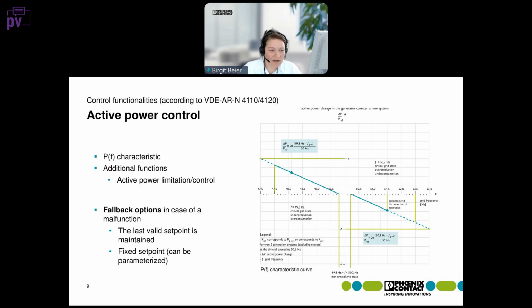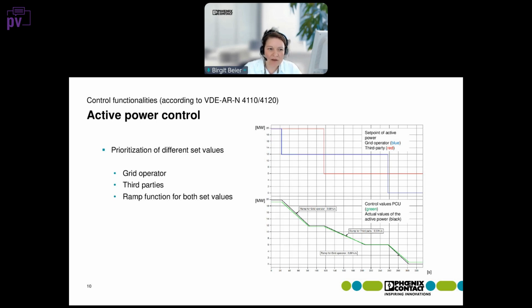So what else do you have? You have some fallback options in case of malfunctions, the last valid set point, for example, or a fixed set point, which can be parameterized. Now we have an example for the prioritization of different set values. On this graphic, you can see the blue line. These are the set points of the grid operator. In this case, the grid operator lowers the value from 20 megawatts to 12 megawatts, and then the PCU ramps down the actual value to 12 megawatts. Now the third party or energy off-taker also lowers the value, and then the PCU will lower the value to 6 megawatts, whichever value is the smallest, to protect the grid.